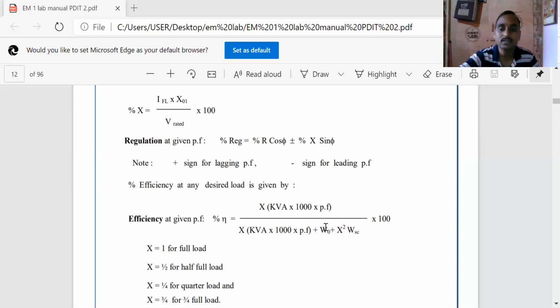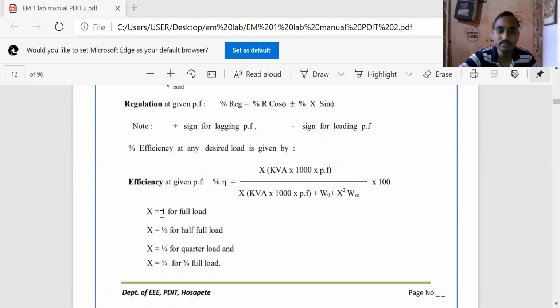So we have calculated these from the readings obtained from the observation table, and X is the load factor. So that can be taken for individual calculation. First time you take X is equal to 1 for full load, next X is equal to half for half load, X is equal to 1/4 for quarter load, and 3 by 4 for 3/4 load. Okay, so depending upon the load factor, we need to calculate X here, and X square here. That can be substituted in the formula to find out the efficiency of the transformer under different load conditions.